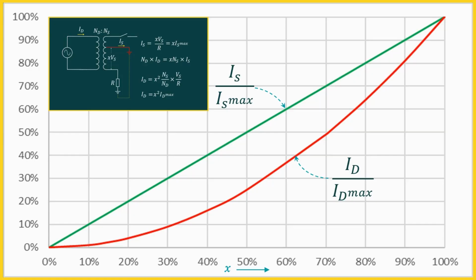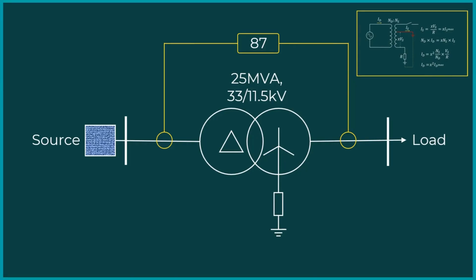This relationship is key to understanding why the differential relay fails to operate for most faults occurring on the star winding. To understand it in detail, let us consider a specific example. Take a 25 MVA, 33 by 11.5 kV transformer. This transformer is equipped with a differential protection. The delta side CT ratio is 500 by 1 ampere and star side CT ratio is 1300 by 1 ampere.